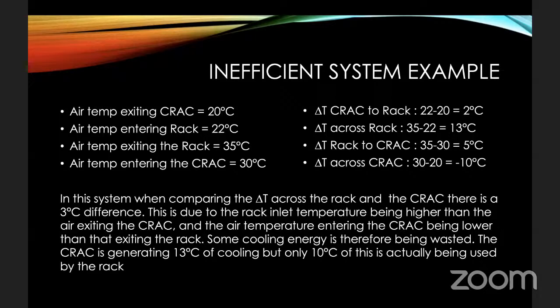Across the rack, 35 exit, 22 coming in. You can see now, this is the same exit temperature as we had in the previous example, but the air coming in is 2 degrees higher, which means our delta T is now 13 instead of 15. And then we have a decrease in temperature from the rack to the CRAC. That's 35 and it's 30 when it reaches, which means that we have lost another 5 degrees there. So now the air entering our CRAC is 30 degrees and the air coming out is 20, which means we now have 10 degrees.